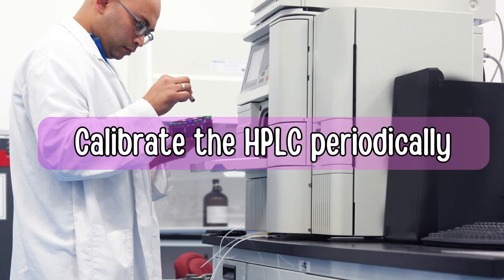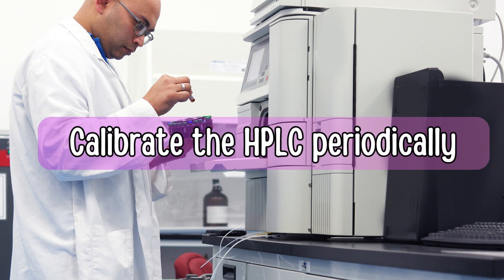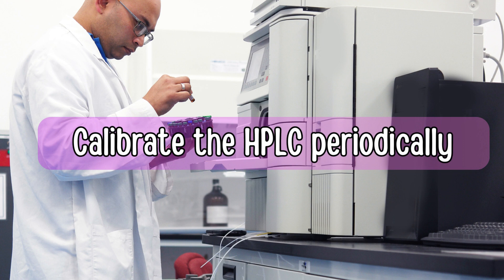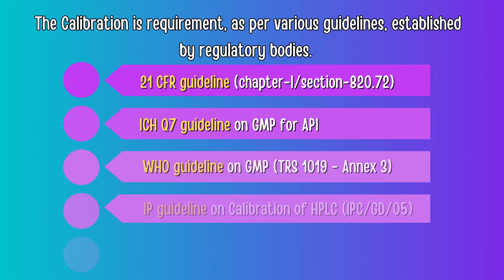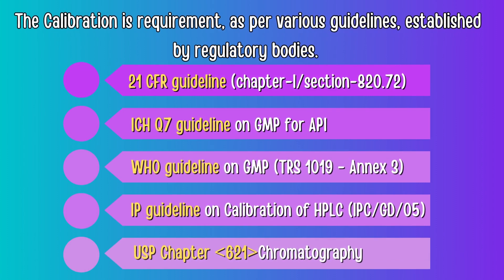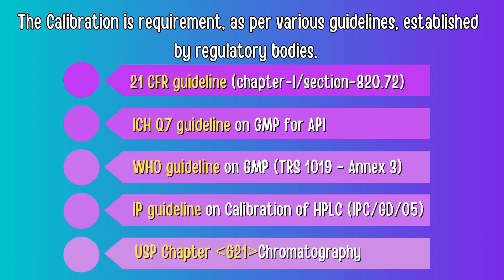Due to its continuous usage, its performance might be impacted. That is the reason it is necessary to calibrate the HPLC periodically to get accurate and reliable results. Also, calibration of instruments is a requirement as per various guidelines established by regulatory bodies, such as 21 CFR, ICH Q7 on GMP for API, WHO guideline on GMP, IP guideline on calibration of HPLC, and USP Chapter 621, which gives general requirements for chromatographic procedures including HPLC.